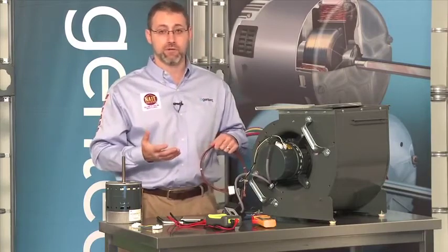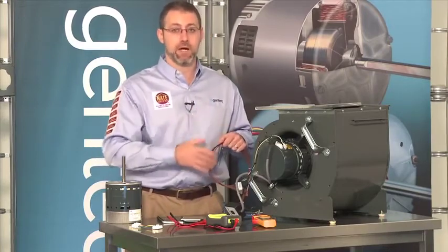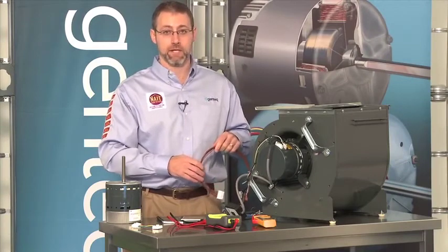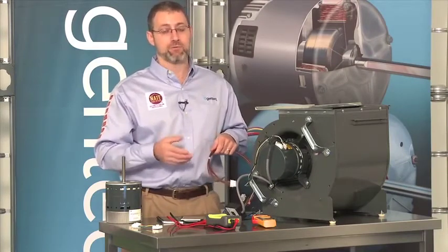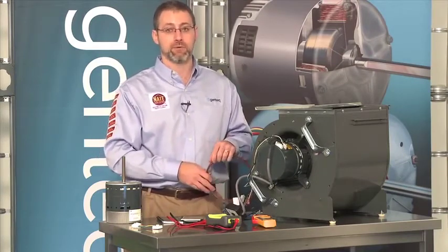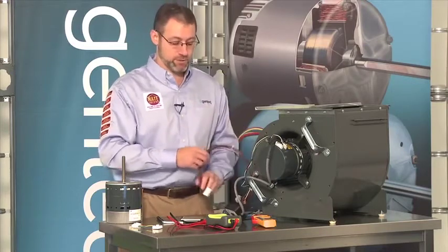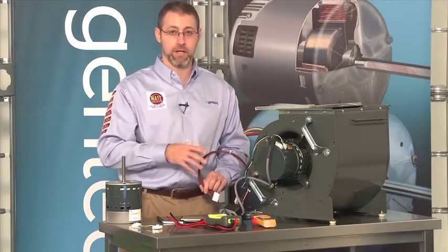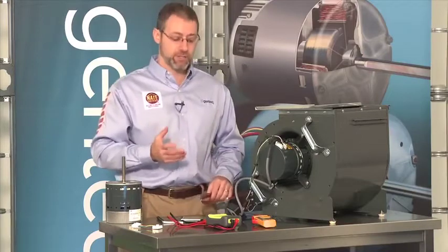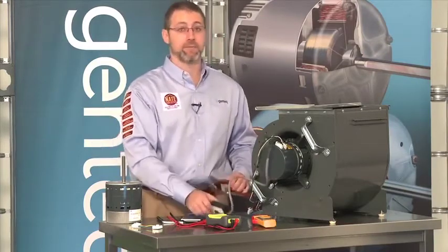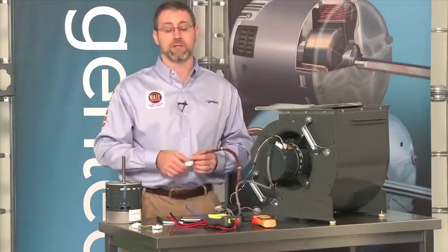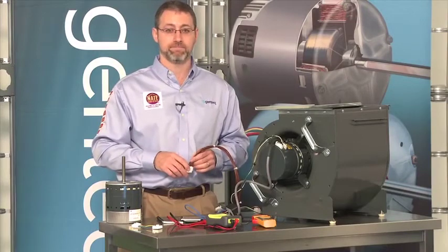If all of those things are good, yes, we could have a problem with the circuit board in the HVAC system. And in that case, we would need to use the OEM manuals that come with the system to troubleshoot the communication on that board. And I should also mention that some manufacturers make tools like the TechMate for troubleshooting this communication on their systems.